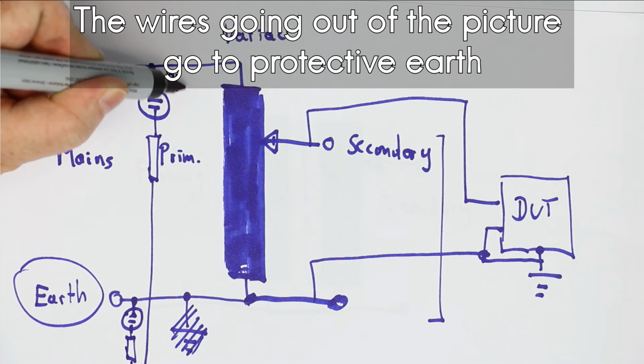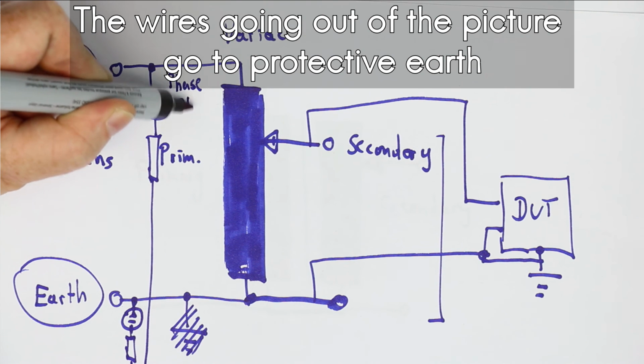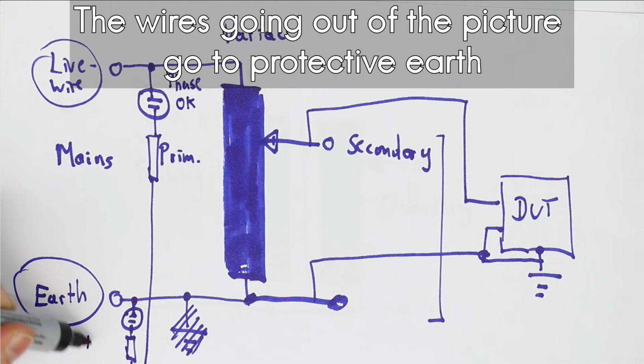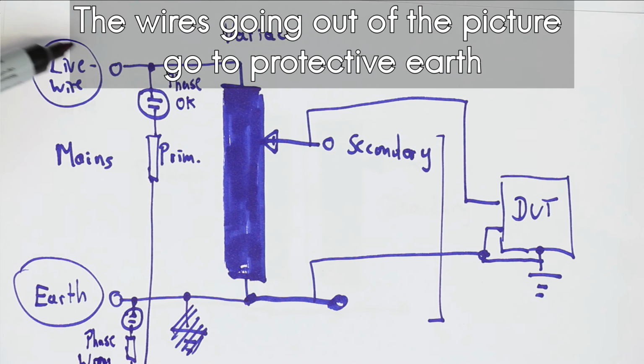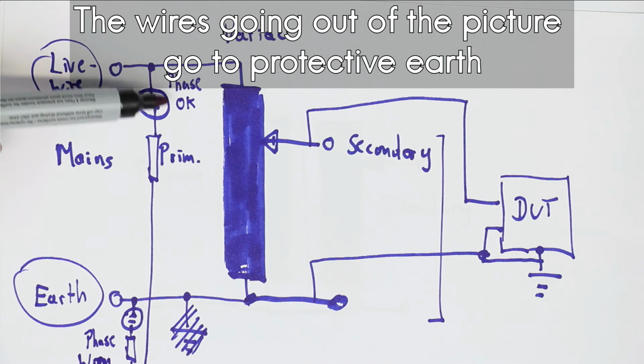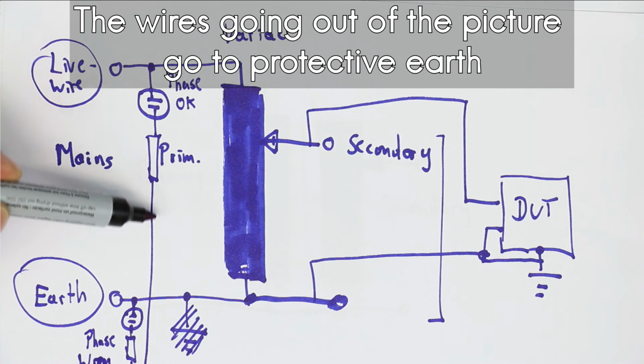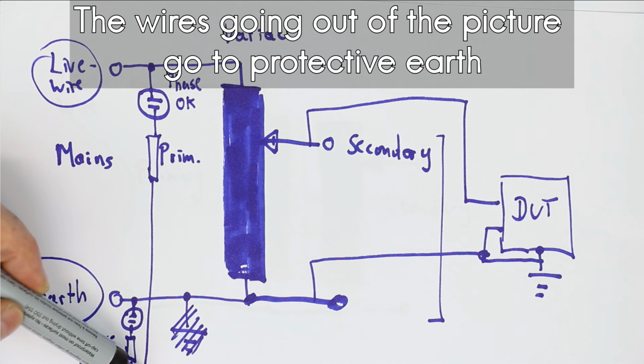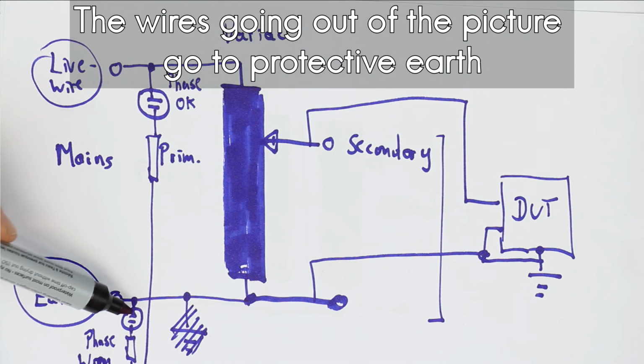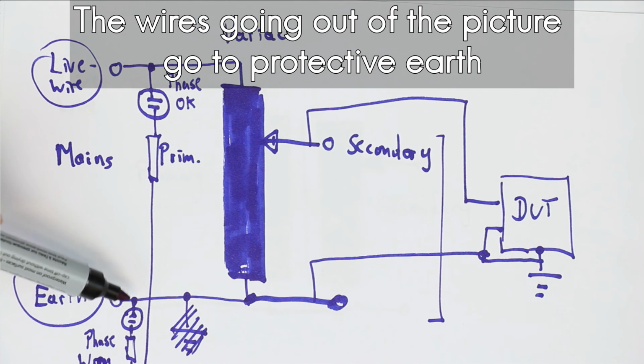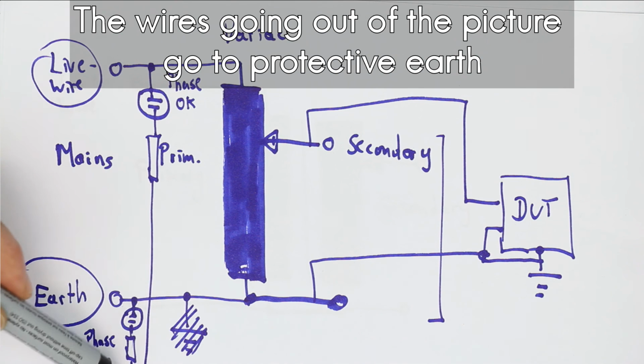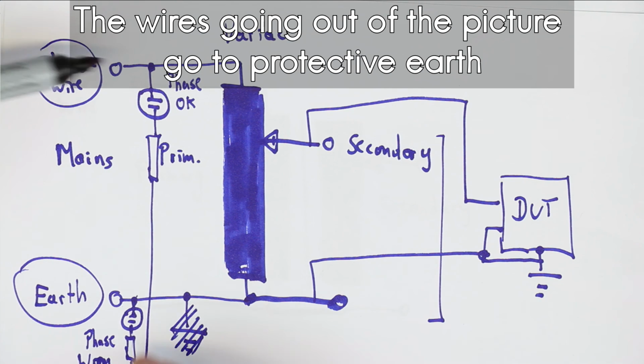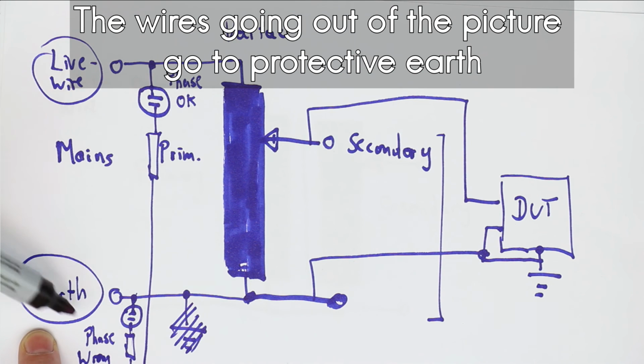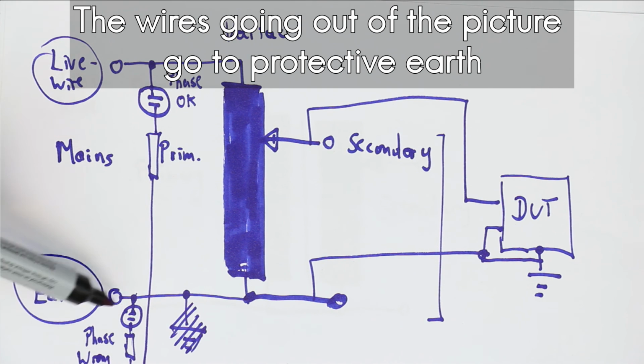This one here is designated in my construction as phase OK, and this is phase wrong, because if the Variac is connected the right way, the glow lamp would light up here, since we have a path down to ground, and the phase wrong lamp cannot light up simply because both connections are at earth. If we interchange live wire and earth input, then the phase wrong lamp would light up.